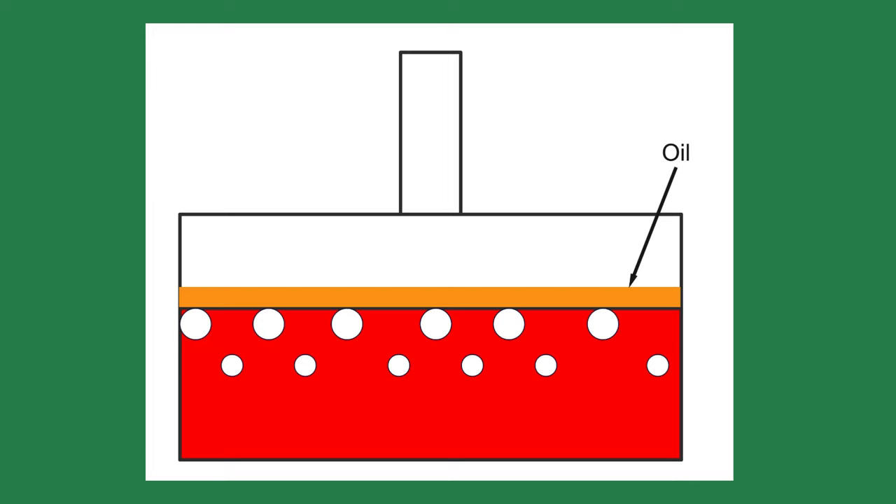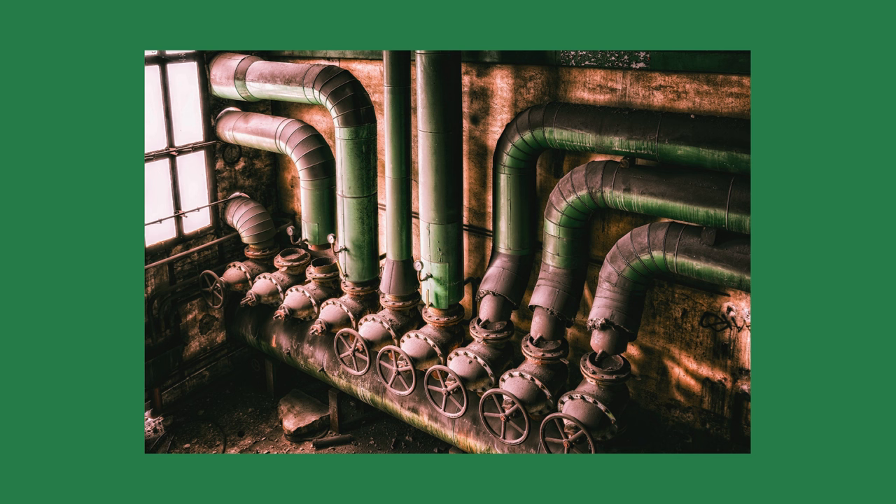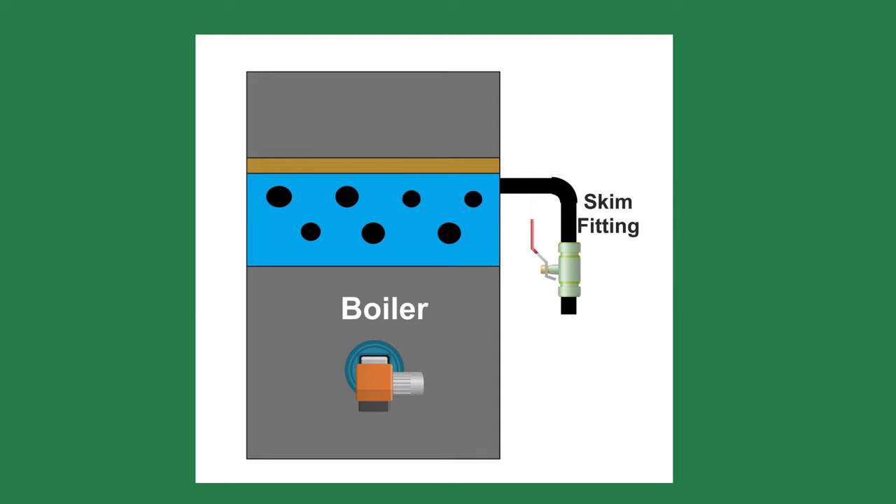How do we get oil in the boiler water? The oil may be from threading oil from pipes, nipples, or pipework that was recently done, or even from boiler components which had leftover oil from the factory when they were machined. The oil has to be removed to allow the boiler to operate properly. This is sometimes challenging as the oil will stick to internal boiler surfaces. I've had success by building the steam pressure in the boiler, shutting off the burner, and doing a surface blowdown.